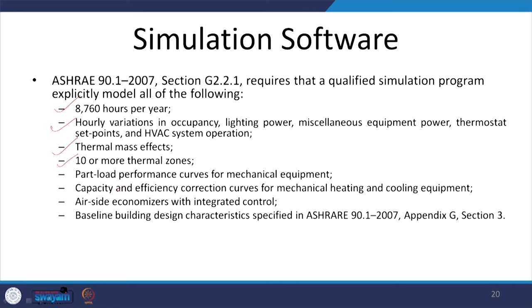It should be able to model the part load performance curves for mechanical equipments and capacity and efficiency correction curves for mechanical heating and cooling equipment. It should be able to model the airside economizers with integrated control, and the baseline design characteristics as specified in ASHRAE 90.1. So, these are the specific requirements of the simulation software as per 90.1, and there are several simulation softwares available in the market. Several of them are free to use.